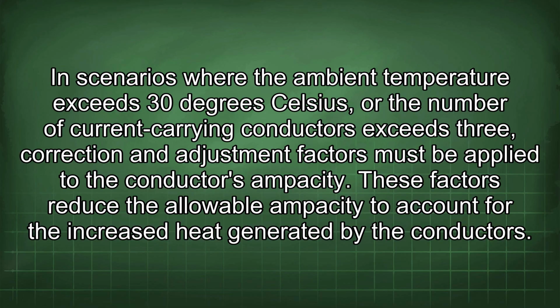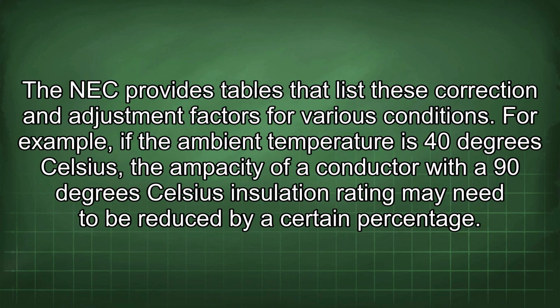In scenarios where the ambient temperature exceeds 30 degrees Celsius, or the number of current carrying conductors exceeds 3, correction and adjustment factors must be applied to the conductor's ampacity. These factors reduce the allowable ampacity to account for the increased heat generated by the conductors. The NEC provides tables that list these correction and adjustment factors for various conditions. For example, if the ambient temperature is 40 degrees Celsius, the ampacity of a conductor with a 90 degrees Celsius insulation rating may need to be reduced by a certain percentage.